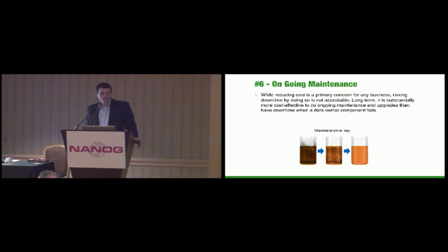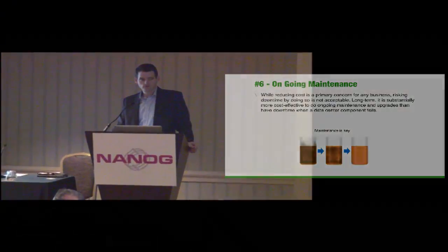I was not part of all the war stories of the guys who have been through these situations, but a couple of stories were interesting to me. One of them was of the hurricanes that happened in Florida. There was a big outage, and the data centers went down, and a couple of the generators didn't kick on. They didn't kick on because the fuel was not clean. Fortunately, the guys who were telling the story, they were the heroes of the story, and their data center did have clean fuel. But it's one of those little nuances that you have to think about.